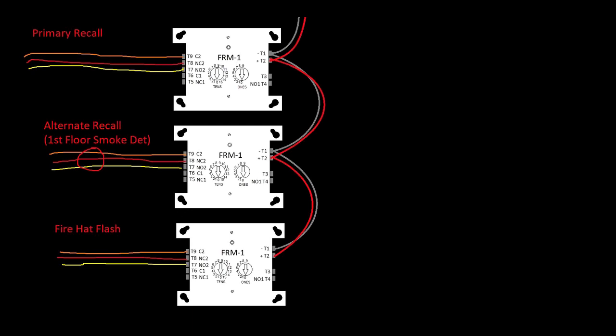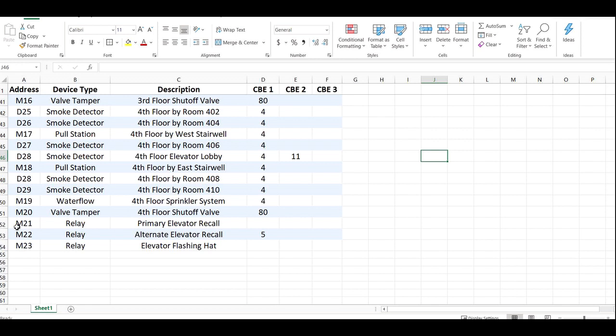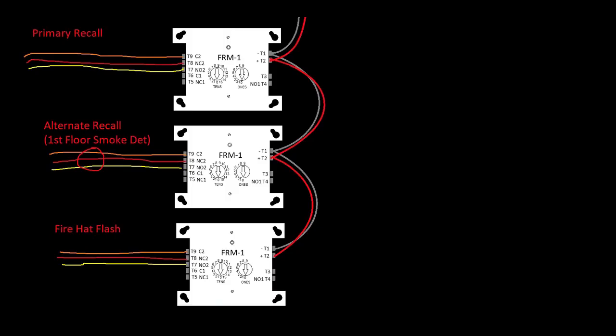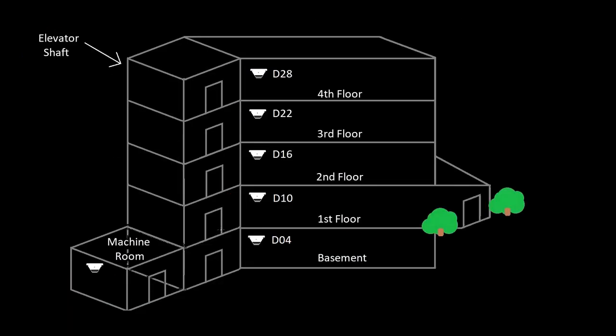So what we care about is we're going to address these relays, right, each one of these. So primary - I added them to my panel or my spreadsheet, but we're going to assume this is like a panel program. I don't know why I have five in there. So I have relay 21, 22, 23, so we would go and add these down the line. You know, this will set the address to 21, 22, 23. And how do we want to zone it? Well, let's see, 21 is primary recall, so 21 is when we're sending the car to the first floor, so that's when the fourth floor, third floor, second floor, or basement activates, right?